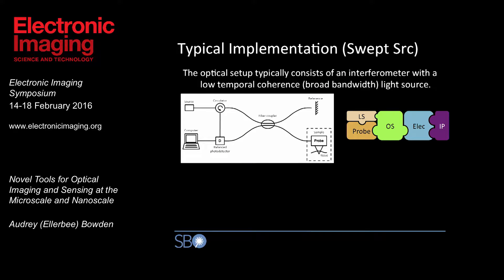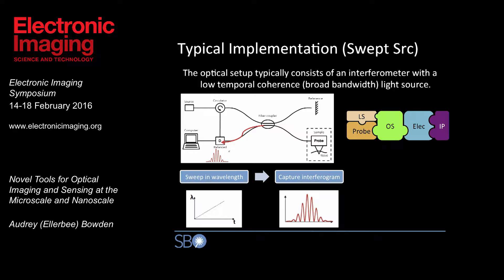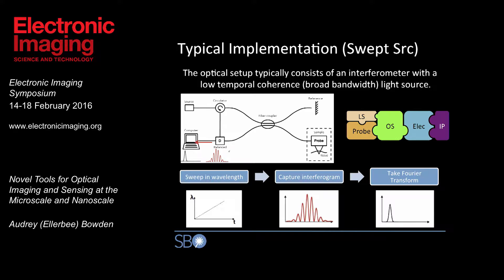A typical implementation of OCT is essentially an interferometer. We have a light source, and that light goes into our interferometer. We use a fiber coupler as a beam splitter to send the light in two directions — to a reference arm and to the sample we're trying to probe. We look for the light that comes back, and that light interferes at the detector, generating an interferogram pattern. One standard approach is using a swept wavelength source, which emits one wavelength at a time, sweeping as a function of time. The interferogram has undulations that encode the relative position of the reference and sample interfaces. To generate the A-scan, we take the Fourier transform.